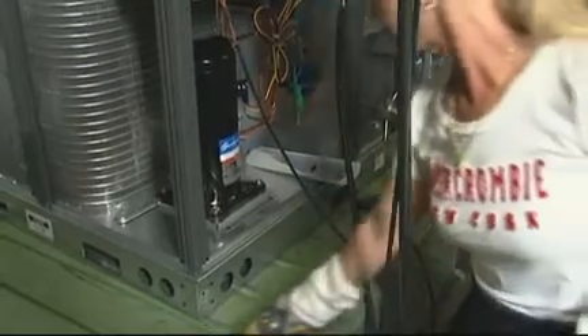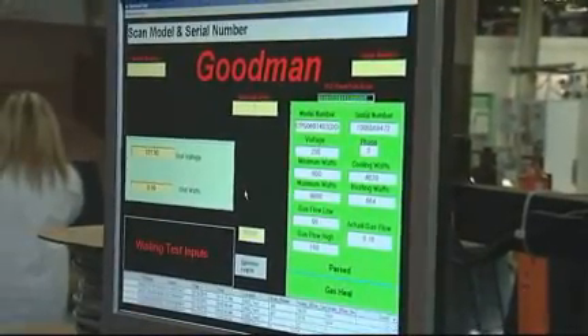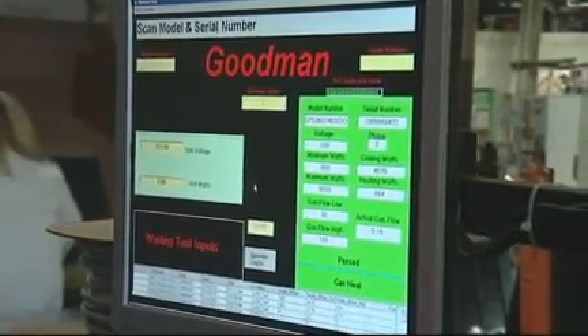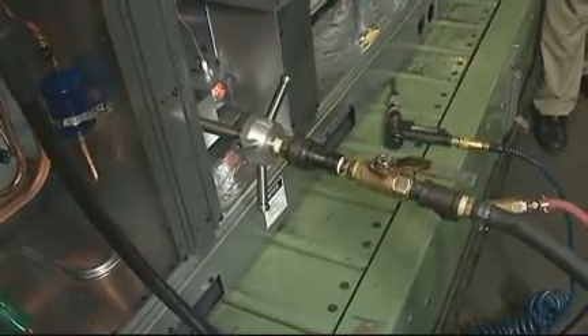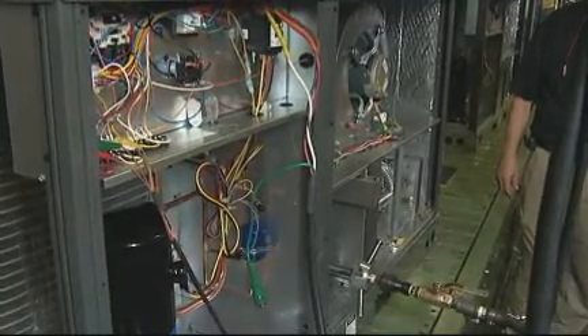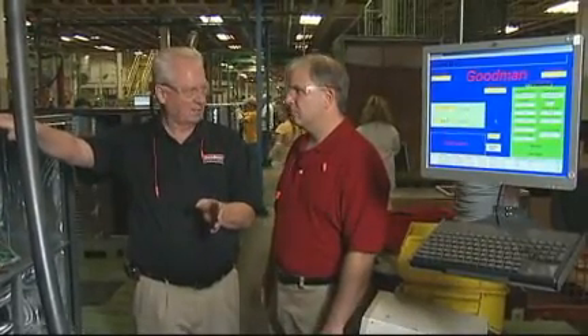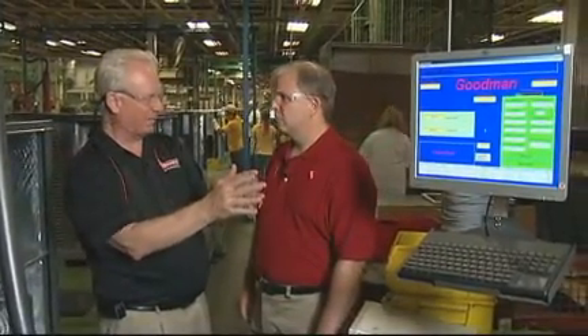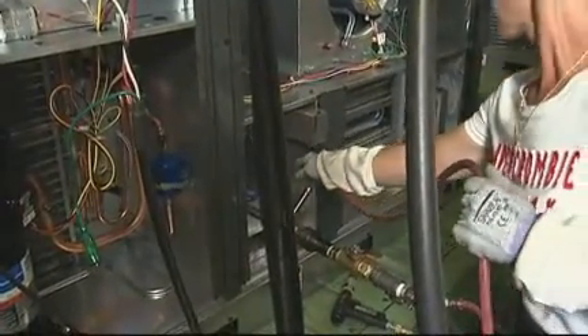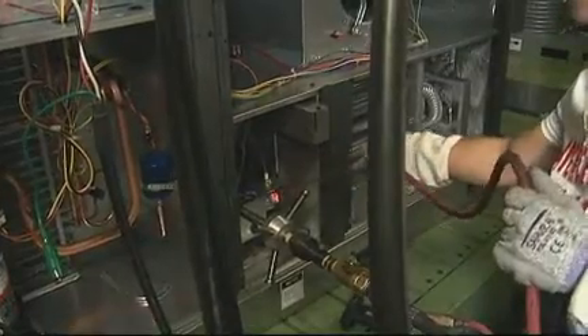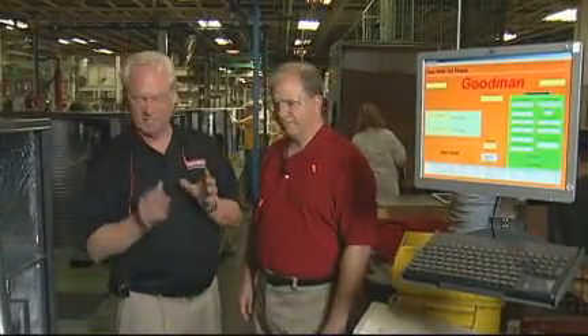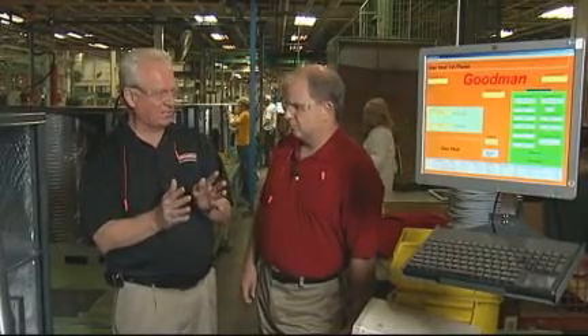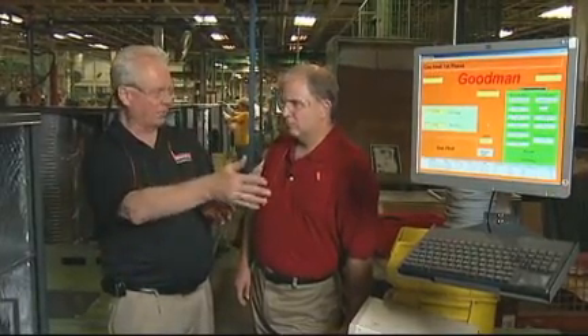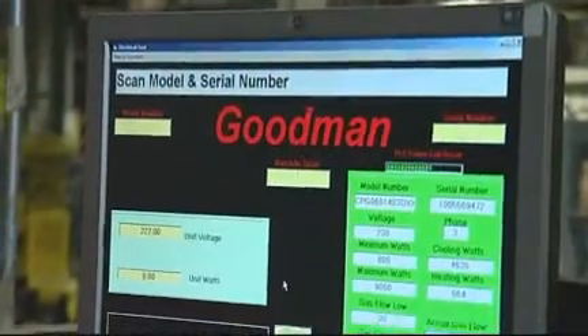That's great. She's scanning the model and serial number, it's feeding into the computer, and now the computer takes over. It's turning on the gas, and it's got a completely pre-programmed test cycle. The blowers come on. Now the important thing about a run test that's controlled by computer is this particular model has all of the run test parameters programmed into that computer. When it goes through the test, it needs to draw the right amount of current when this blower's on. It needs to draw the right amount of current when the compressor's activated. Right. If it doesn't run within the preset parameters of the run test, it'll fail. And the fail record will be stored in the computer. The operator doesn't have to make a decision at all.